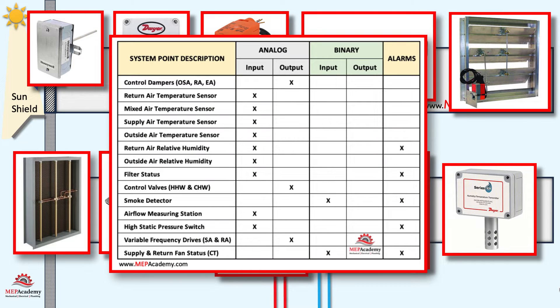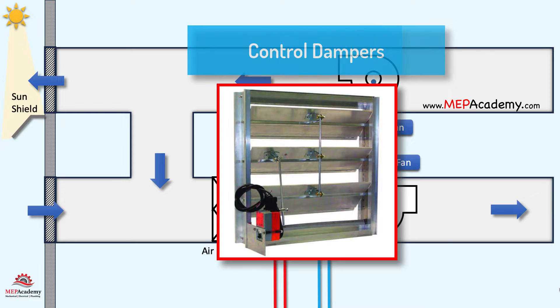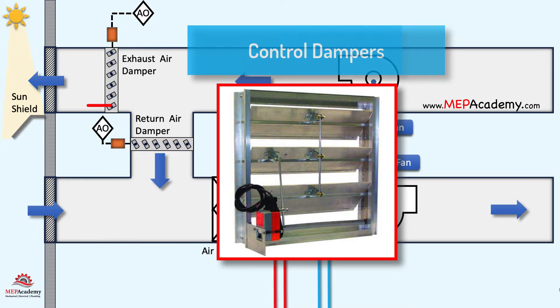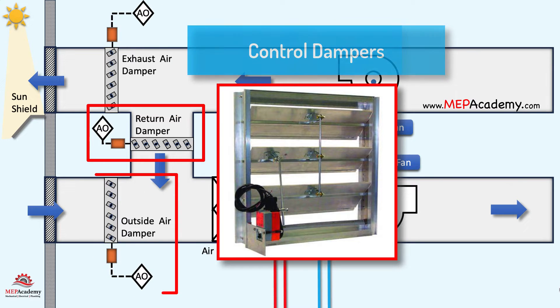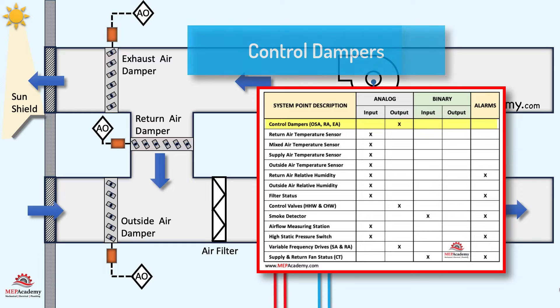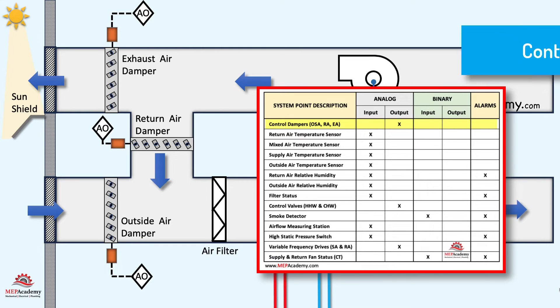We'll also build a controls points list as we add the various DDC components for controlling the air handler. Three dampers are added which include the exhaust air, return air, and outside air dampers. These dampers will have actuators that will allow the DDC system to adjust the damper positions to meet the system requirements. They will be actuated by 24 volts of power.